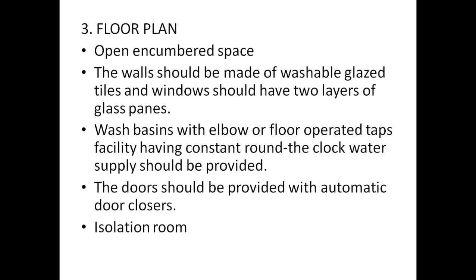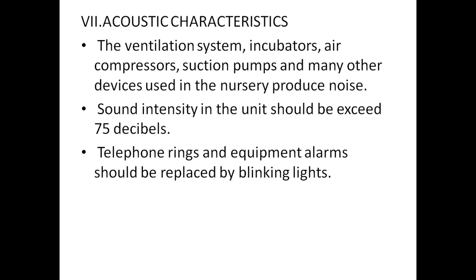Acoustic characteristic: the ventilation system, incubators, air compressors, suction pumps, and many other devices used in the nursery produce noise. The sound intensity in the unit should not exceed 75 decibels. The telephone rings and equipment alarms should be replaced by blinking light. Instead of air compressors, a centralized source of compressed air, oxygen, and suction should be provided.